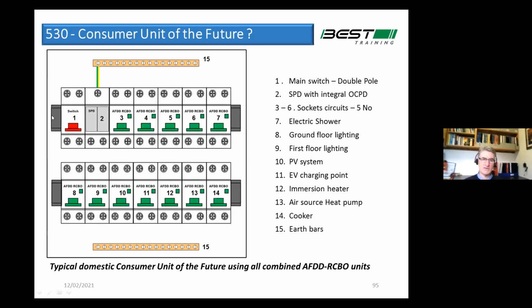So some of the other changes that have occurred: double pole switching is now required in the consumer unit. And obviously, if you're in a normal domestic situation and the consumer unit is right beside the meter cabinet, this has to be a circuit breaker. So it's a single pole plus neutral circuit breaker. SPDs, I mentioned earlier on, it tells you that they're not really mandatory, but you have to go off and do a risk assessment, as we explained before. I can't see anybody bothering their Barney doing that. I can just see most people saying just put it in. It's another 30 euros added in.